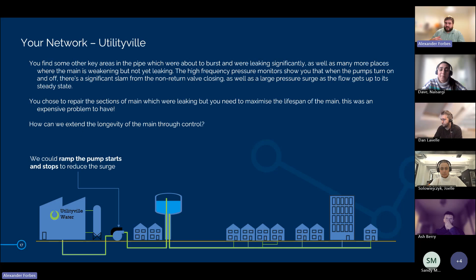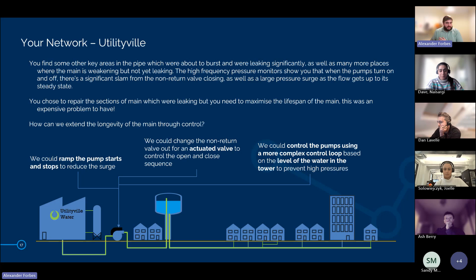We could maybe control the pumps using a more complex control loop based on the level of the water in the tower, for example. That would completely mitigate the surge problem, and it means that we would be running at the minimum pressure that we needed to be, potentially. And we could change the non-return valve out for an actuated valve and control it to open and close automatically rather than getting it to do it based on the flow rate going through, because we can see that there's a lot of slam coming from that non-return valve. So these are some stuff we could do specifically for control, but you're absolutely right. The solution here is replace the main with something that's not going to corrode in the soil that it's in. But unfortunately, the main laid in the ground was damaged by the soil. It's too expensive to relay the entire main at the moment, unfortunately.